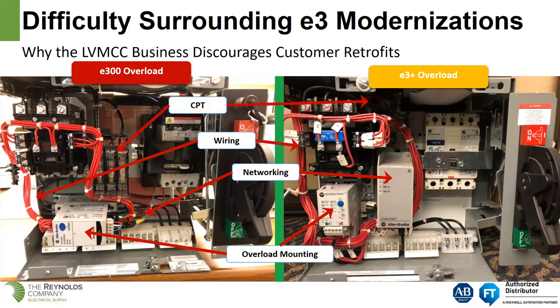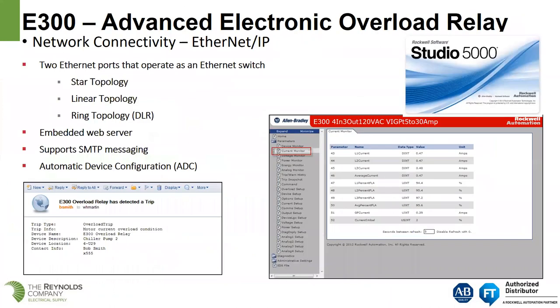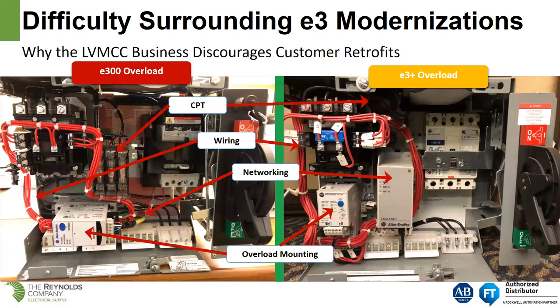Regarding the CPT — the fuse blocks for the control circuit transformer — in order to make the E300 fit, they went to a single three-pole fuse block. For an E1 Plus overload relay, you would have a 480-volt fuse block and 120-volt fuse block on either side, and those would have to be relocated. Also, once you get beyond a size 2 contactor, the E300 goes back to being a direct mount. So for size 3, size 4, and size 5 — across the line starter, reversing starter — the E300 would be direct mounted to the contactor.